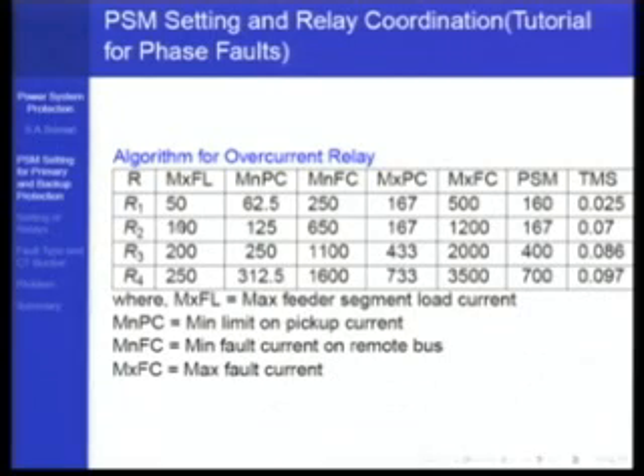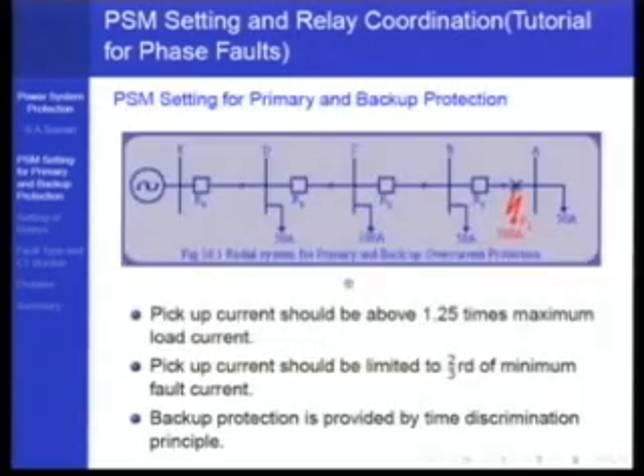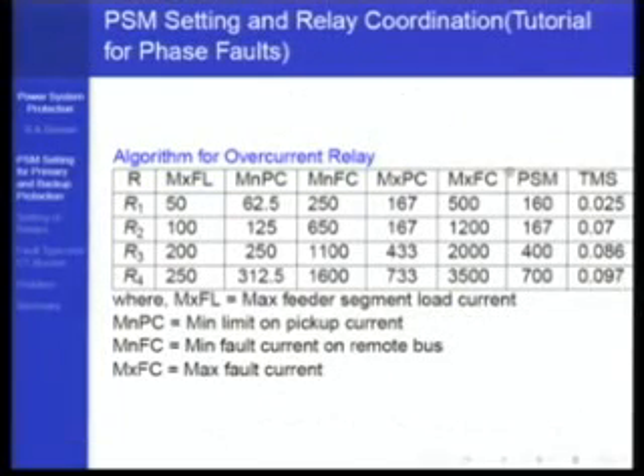In this case we have chosen R2. Now relay R2 sees a load current of 100, so its minimum pickup current should be 125 amperes. And what is the minimum fault current that it sees? On its primary section it sees a minimum fault current of 650 and a maximum of 1200, on this section BC. But this relay has to back up all the way up to A. It has to provide not only primary protection here but also backup protection all the way up to point A. So for setting purposes you have to look at the minimum fault current seen by relay R1, which it is backing up, and that current is 250 only.